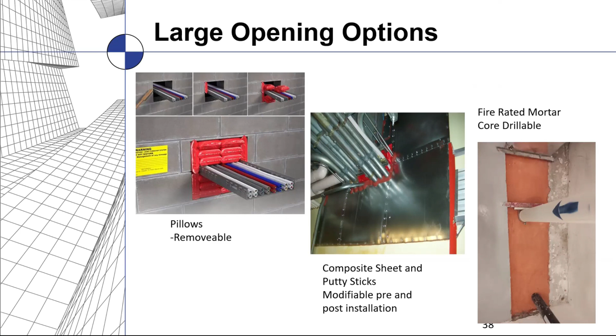More permanent solutions are composite sheets - large 3-foot by 3-foot stainless steel sheets with firestop intumescent materials applied, which you can stitch together to create quite large openings. Or you can use fire-rated mortar, used horizontally or vertically, just like concrete material except completely fire-rated - you can core drill through it and run pipes through it, or place pipes in there and pour the concrete around it to seal it all up.